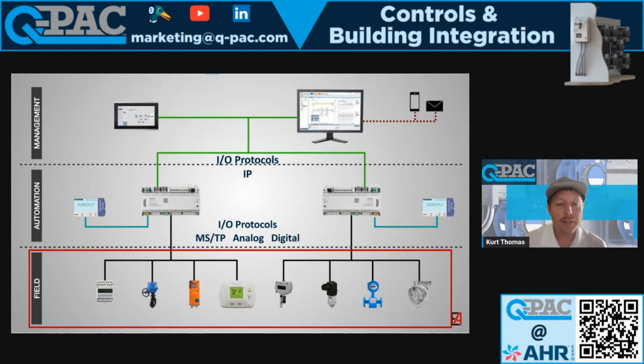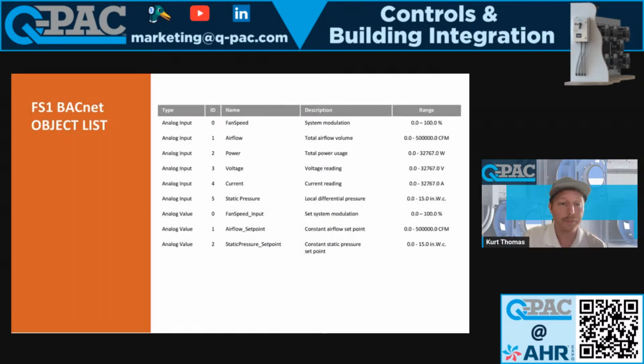Yeah, so you have all of your devices down below in the field, your digital and your analog, your MSTP, whether it's BACnet or whether it's Modbus, and then they feed the building automation system controllers and PLCs, right? So that's where all the logic is done. That's where your controls contractors will spend a lot of time making sure everything's balanced, creating the touch points that the actual management team will need to use. So if they need to change the speed of the fans or change set points, then they can do that in the management level, where you connect all of your HMIs and everything. So that's your typical stack, and it's a pretty simplified version of your building automation system.